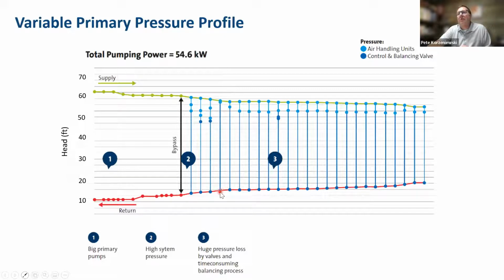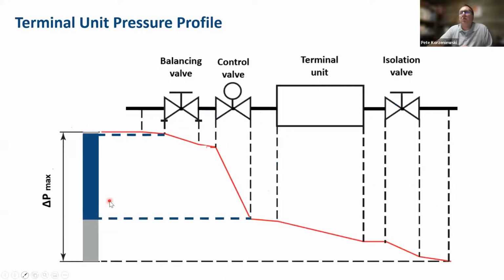We enter the return back to the chiller to pick up more chilled water energy to start the cycle all over again. If we take a little closer look at the terminal unit itself to see what the pressure profile is there, we have here again the P max at design flow for this particular air handling unit, and then the component talked about: the control valve, our terminal unit, the heat exchanger itself, and then the isolation valve.